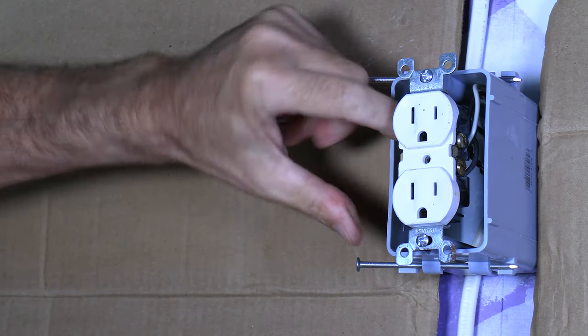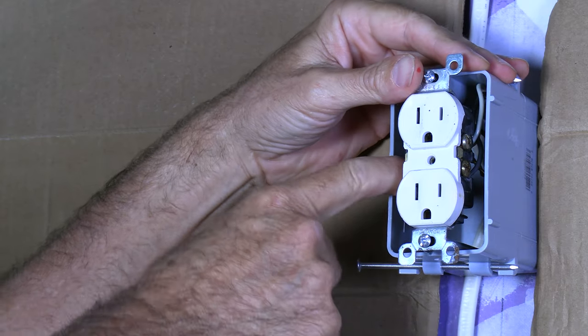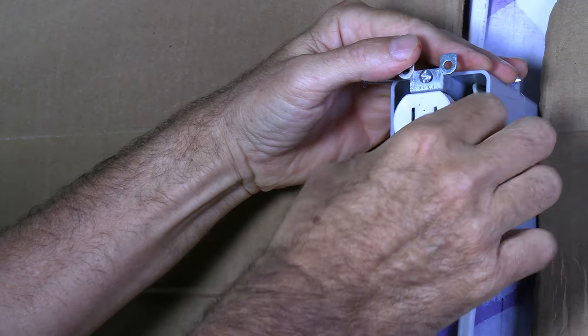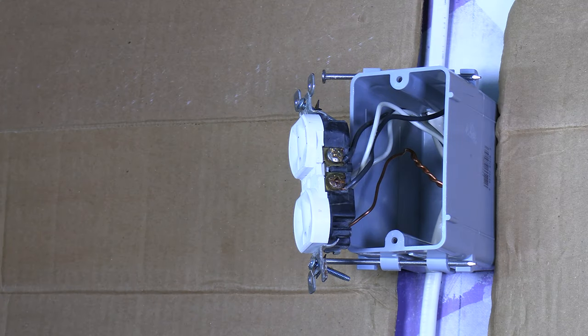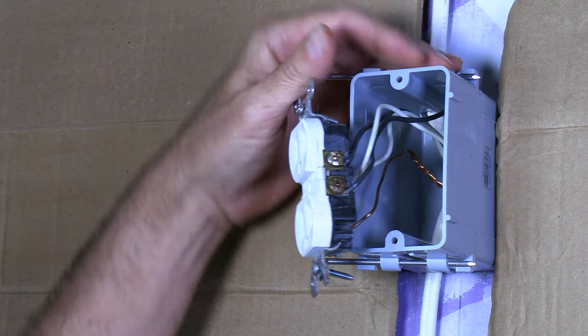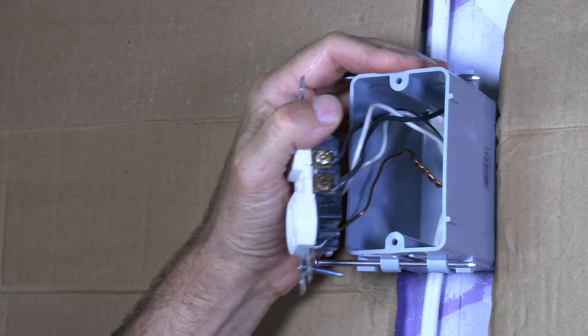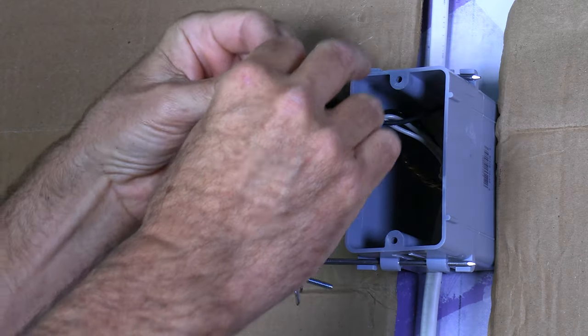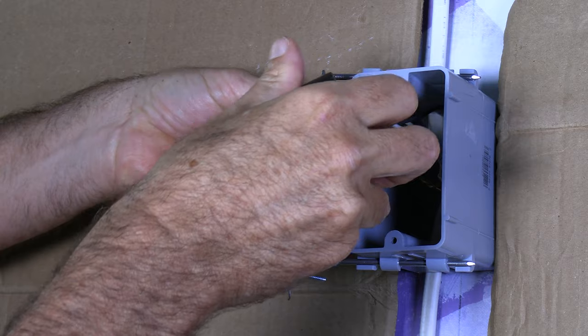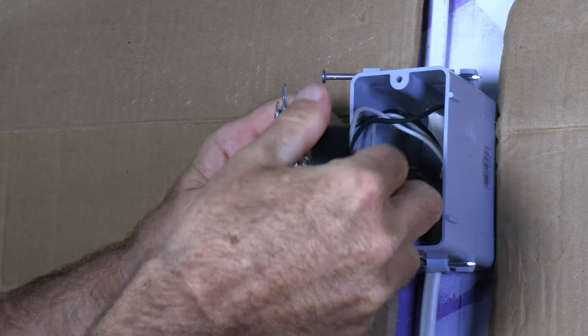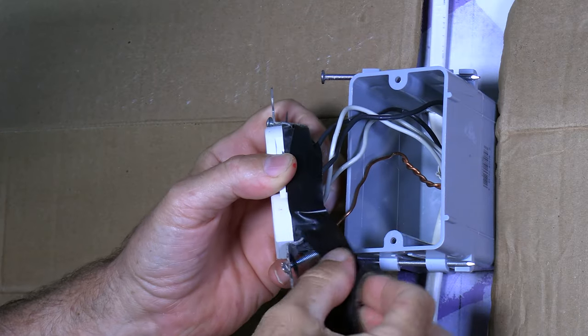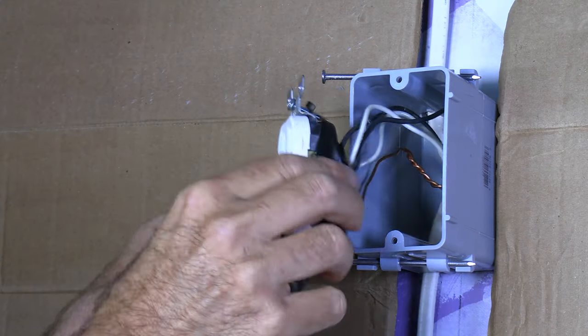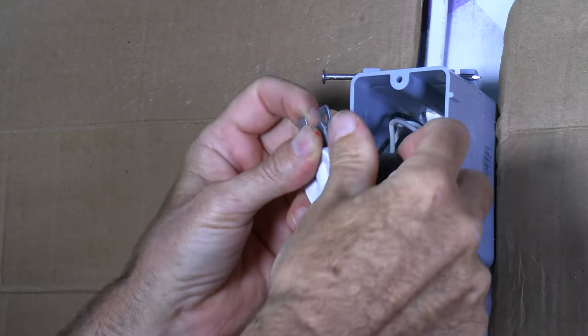Make sure when you're done, you look inside with a flashlight and just make sure your wires are not touching places where they're not supposed to be touching. One thing that you might want to consider is if you're replacing your plug where there's a metal box, you might want to consider wrapping the plug with electric tape, kind of like this. All right. Go around the screws and just do this maybe two times just to insulate this from the metal box.